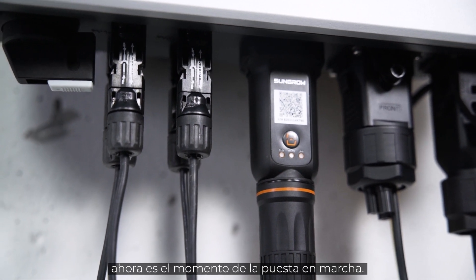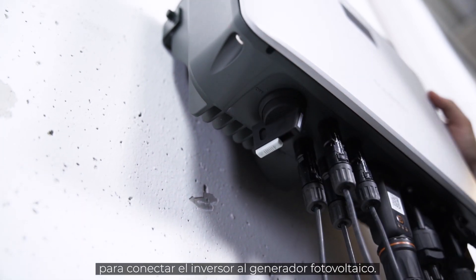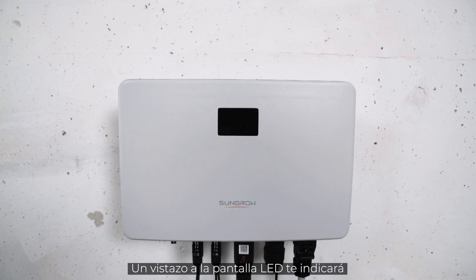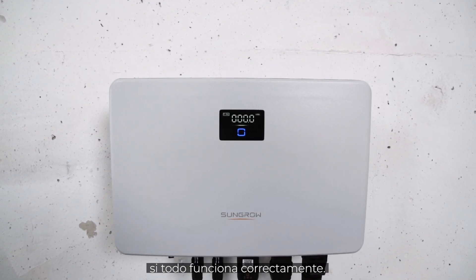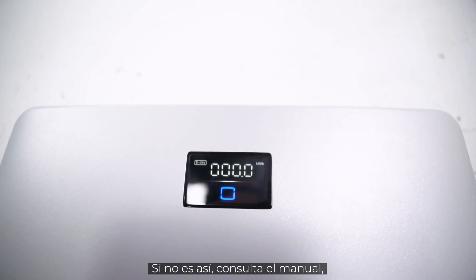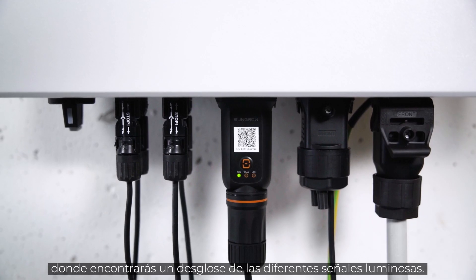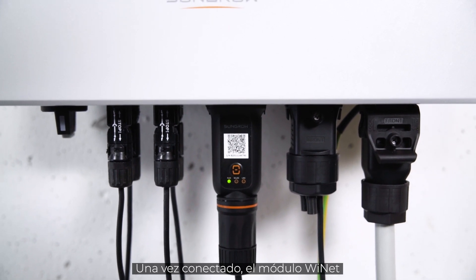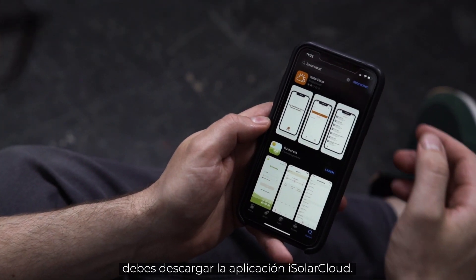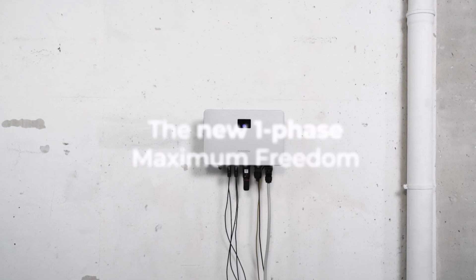Now it's time for commissioning. First, you have to set the DC switch of the inverter to the ON position to connect the inverter to the PV generator. Next, you have to switch ON the AC circuit breaker. A look at the LED light tells you if everything works properly. If the light shines continuously blue, the inverter is ready for use. If this is not the case, please refer to the manual where you will find a breakdown of the different light signals. When connected, the WiNet module takes some minutes to fully boot. To finalize the setup, you need to download the iSolar Cloud app. You may find a detailed commissioning video on our YouTube channel.